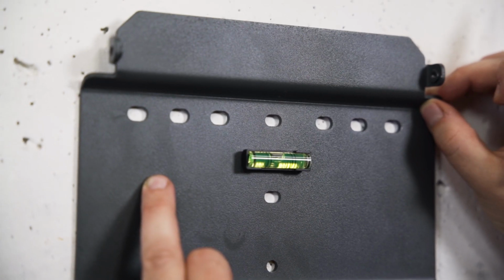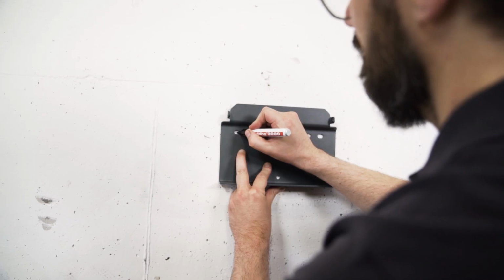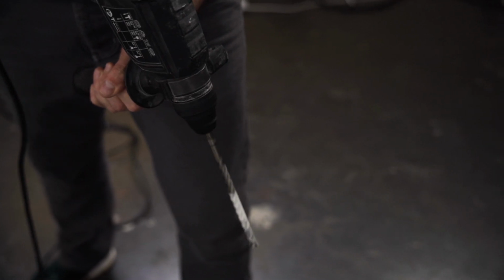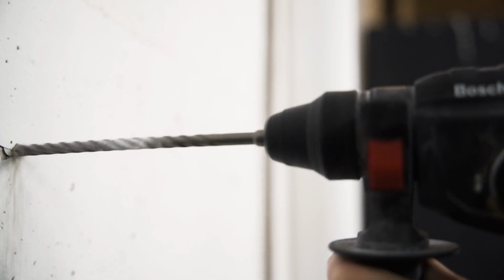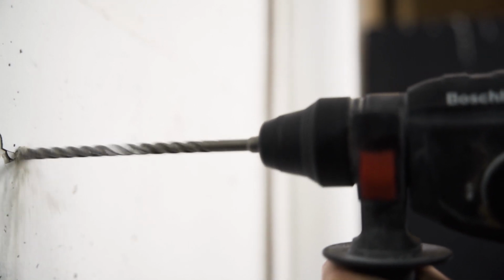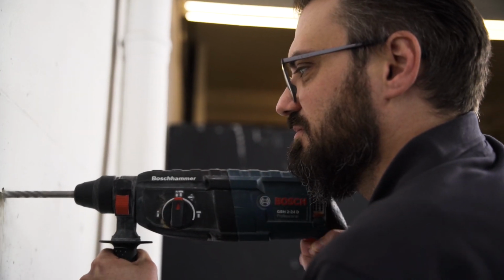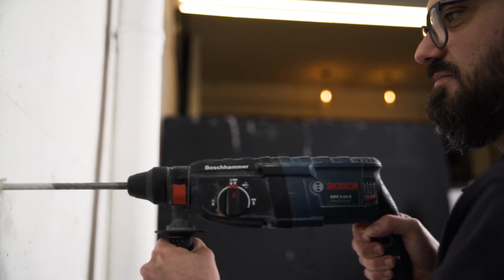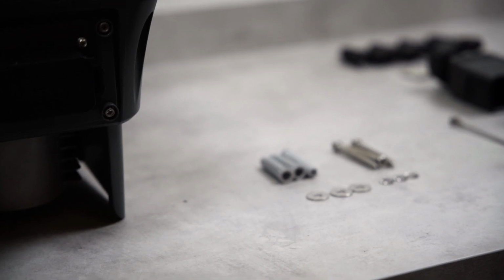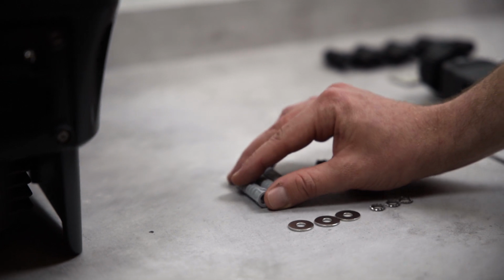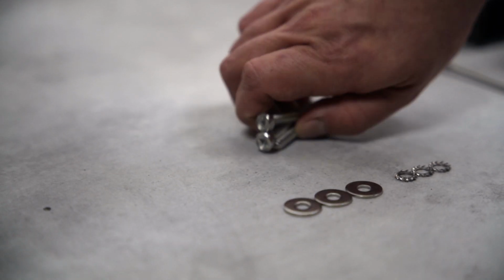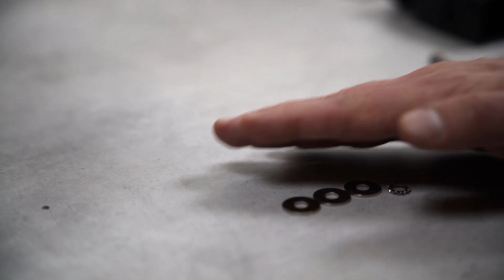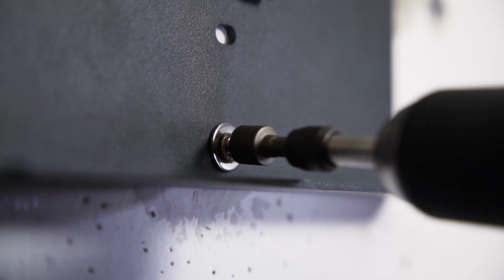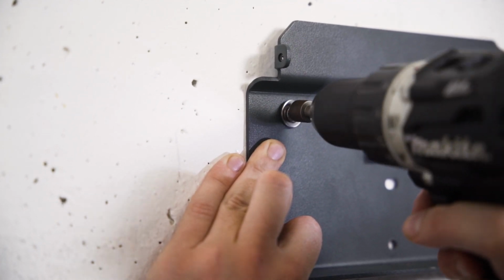Before you start drilling, you should make sure that there are no wires running through the wall that you could damage. Take your drill with the 10mm drill bit and drill at least 70mm deep into the wall at the marked points. The dowels for mounting the inverter on the wall are included in the delivery. You will also need a cordless screwdriver for attaching the mounting plate. The required screws are part of the delivery.